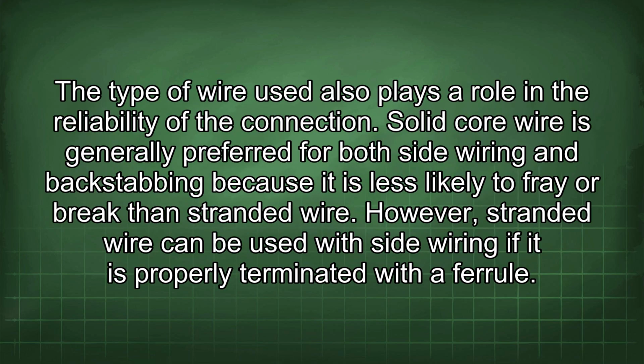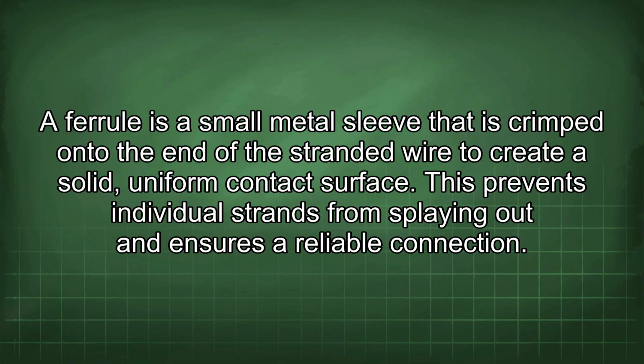The type of wire used also plays a role in the reliability of the connection. Solid core wire is generally preferred for both side wiring and backstabbing because it is less likely to fray or break than stranded wire. However, stranded wire can be used with side wiring if it is properly terminated with a ferrule. A ferrule is a small metal sleeve that is crimped onto the end of the stranded wire to create a solid, uniform contact surface. This prevents individual strands from splaying out and ensures a reliable connection.